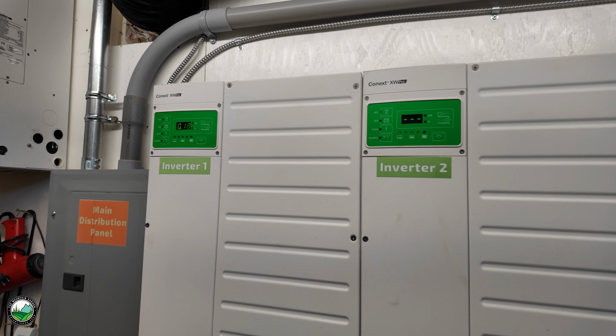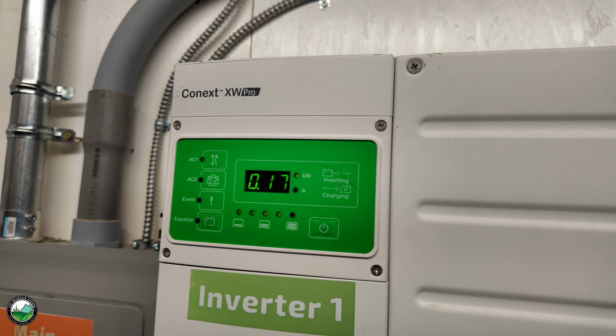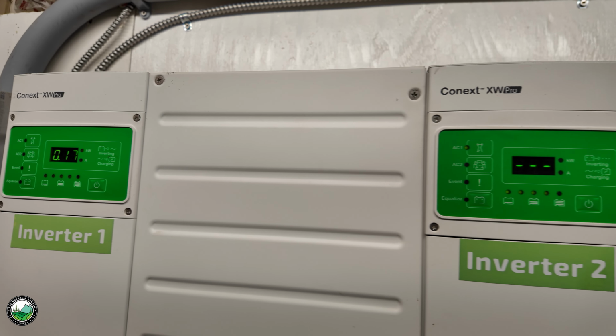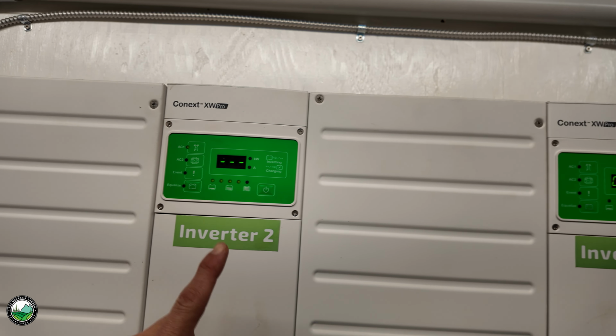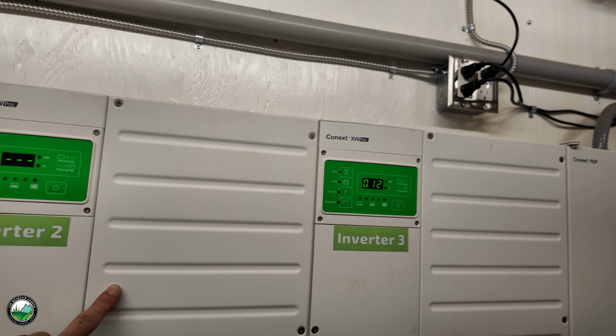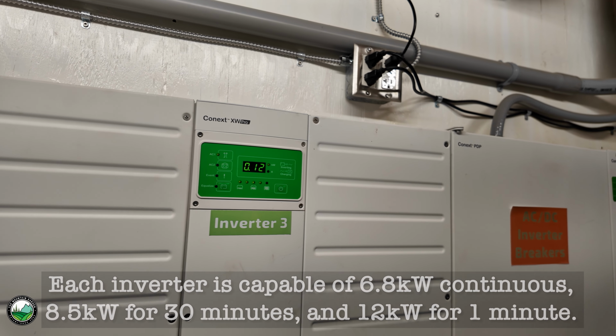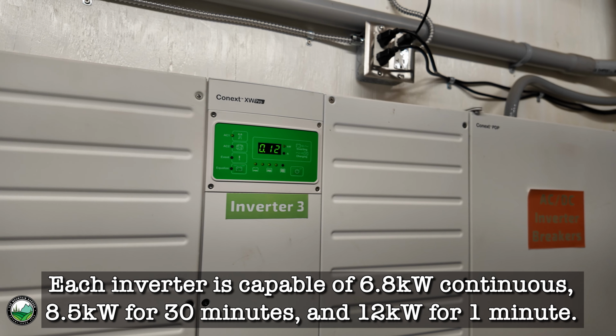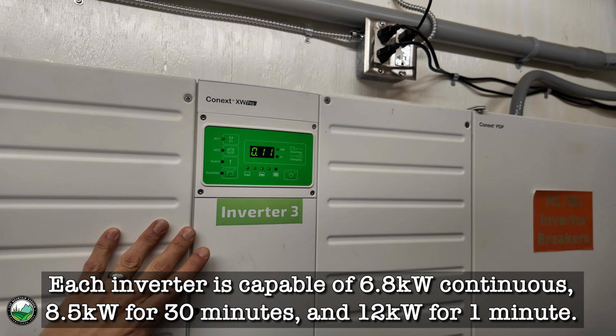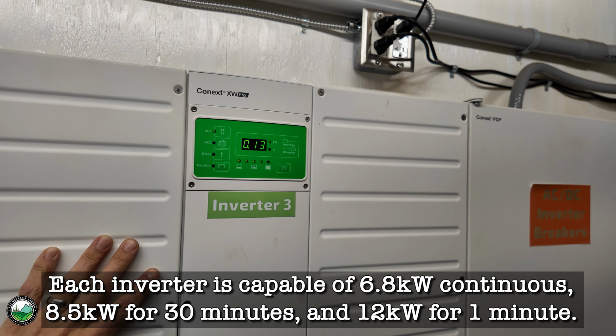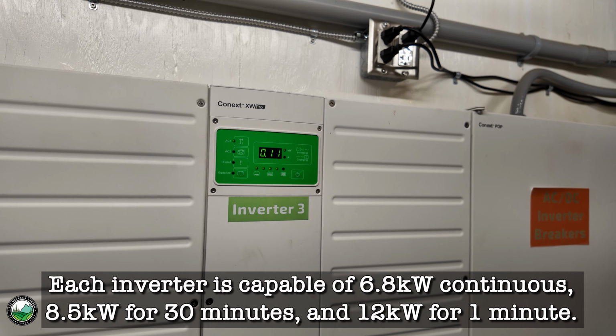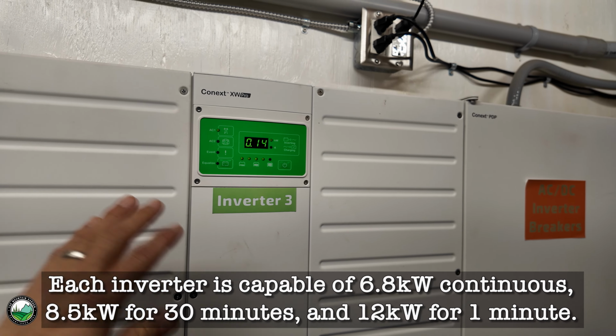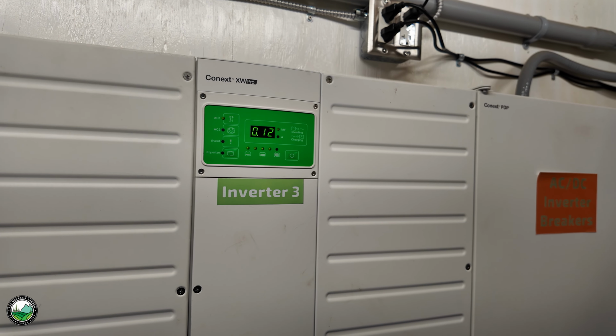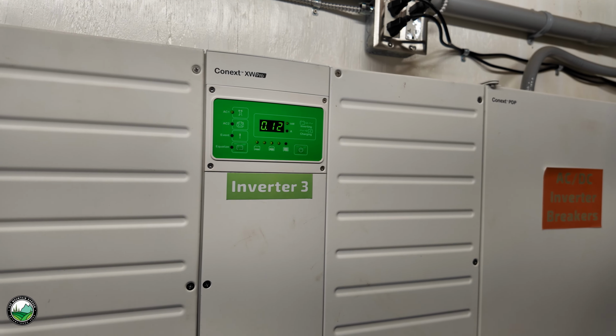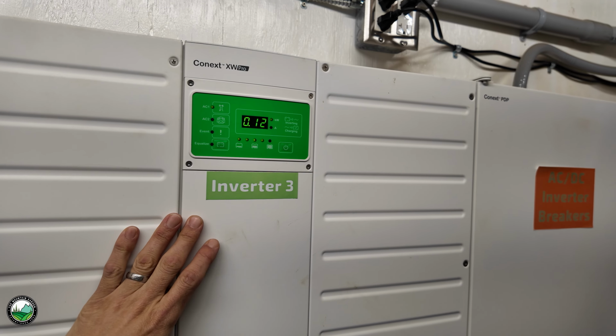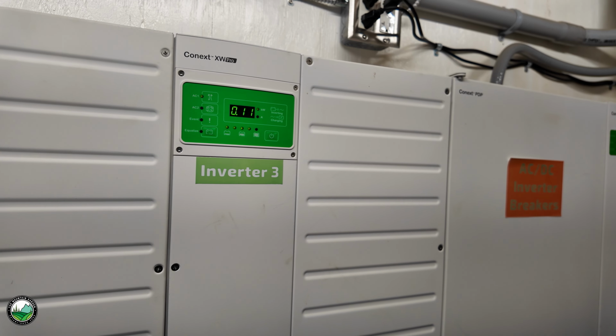Up in the electrical shed, very little has changed. We still have the Schneider XW Pro inverters, 3 of them in a line. Each one is good for almost 7 kilowatts continuous, and each will peak well over 11 kilowatts for quite some time. These are really nice inverters for a 48-volt system because they have a big transformer inside. They can handle some of those bigger starting loads, and even with just one, occasionally drawing 10 kilowatts for not more than 20 minutes or so, they'll handle those larger loads for a surprising amount of time.